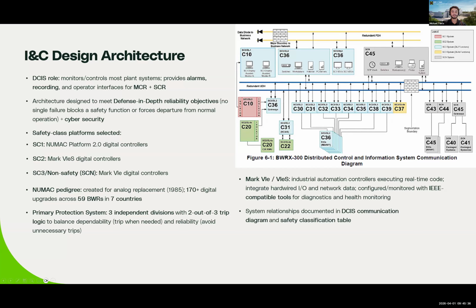The design aligns hardware safety class, and the platform selection is tiered by the safety class. So that's what helps us select the right platform. NUMAC is selected for the highest safety class 1 systems. The Mark VIeS is selected for mid-level safety functions, and the Mark VIe without the S is used for some lower safety class systems or safety class none systems. A key protection feature is the 3-division architecture using 2 out of 3 trip logic to ensure the required trips occur while minimizing spurious trips. And the Mark 6 controller family supports real-time automation with robust configuration and diagnostics, and I think they have a history of being used in BWR plants.